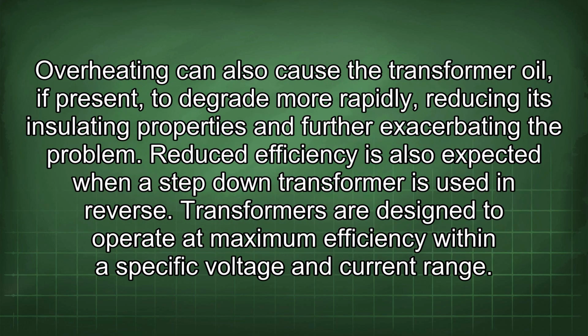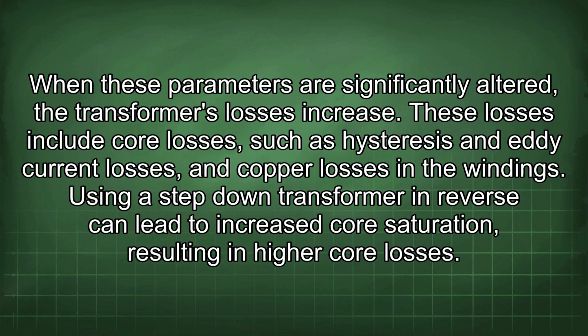Overheating can also cause the transformer oil, if present, to degrade more rapidly, reducing its insulating properties and further exacerbating the problem. Reduced efficiency is also expected when a step-down transformer is used in reverse. Transformers are designed to operate at maximum efficiency within a specific voltage and current range. When these parameters are significantly altered, the transformer's losses increase.